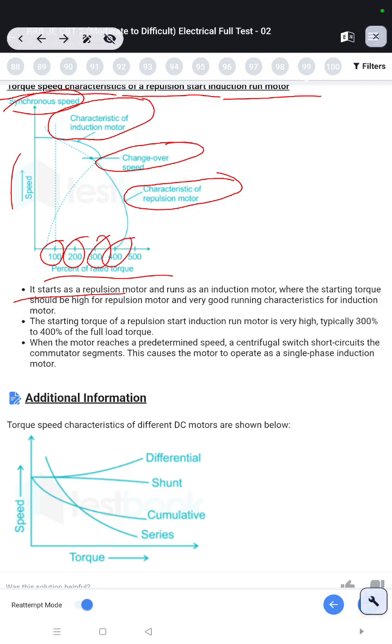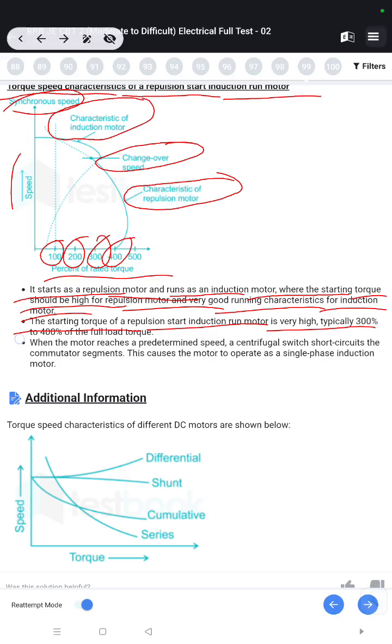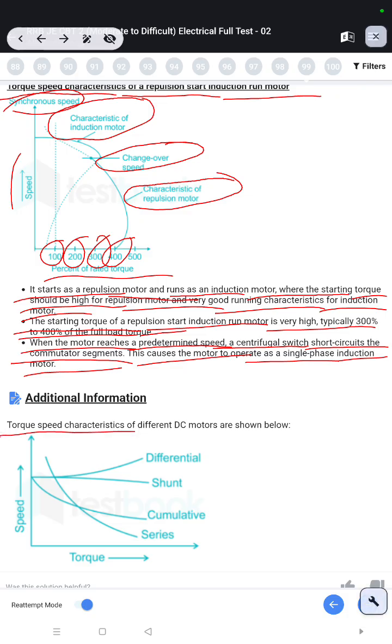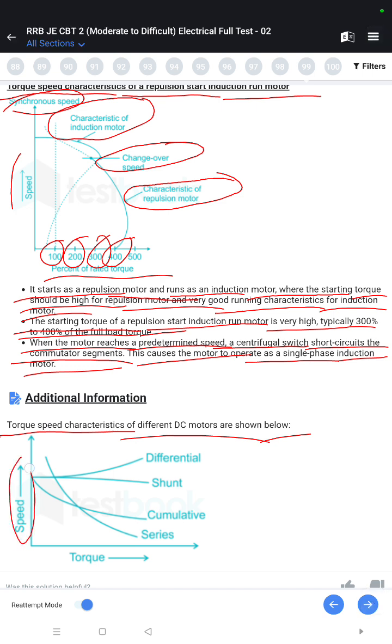It starts as a repulsion motor and runs as an induction motor, where the starting torque should be high for repulsion motor and very good running characteristics for induction motor. The starting torque of a repulsion start induction run motor is very high, typically 300% to 400% of the full load torque. When the motor reaches a predetermined speed, a centrifugal switch short circuits the commutator segments. This causes the motor to operate as a single phase induction motor. Torque speed characteristics of different DC motors are shown below. Speed, torque, differential, shunt, cumulative, series.